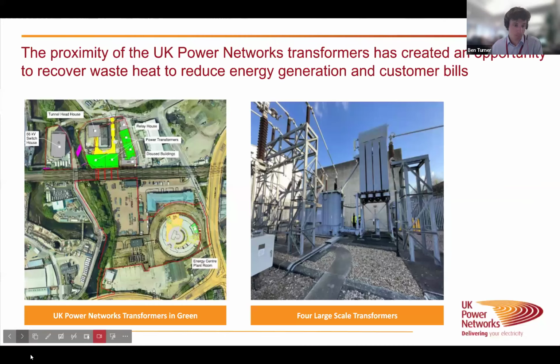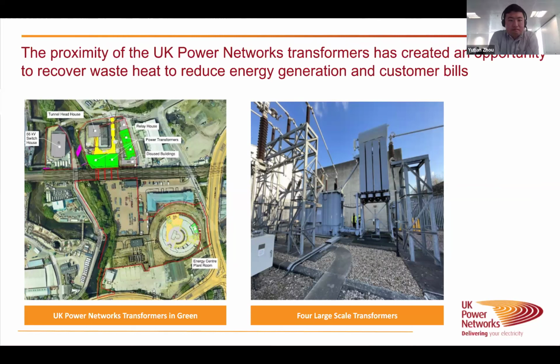Next slide, please. So this housing development is situated in Wandsworth, and it just so happens that over a railway track there is a UKPN substation, and within that substation we have 4 rather large transformers. Now, for those of you that don't work for a DNO, transformers are used for switching voltage, and this can lead to quite a buildup of heat. The traditional way that we get rid of that heat is you have oil circulating throughout the transformer, and that's sent to essentially an air-cooled radiator where you dispel that heat into the atmosphere. So that is potentially quite a lot of waste heat that we could use for this housing development. I'll pass on to Yuchen, who will explain in a bit more detail.